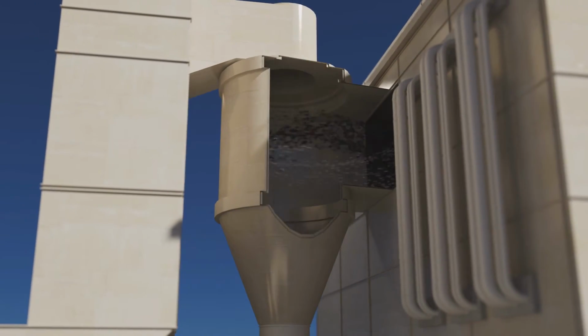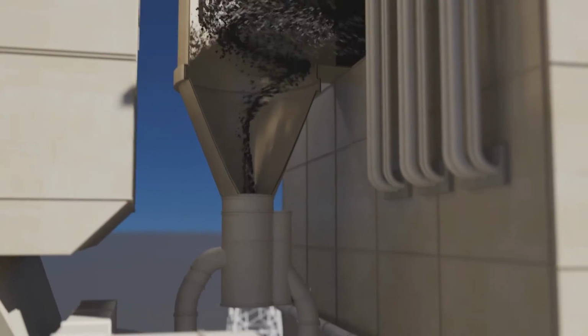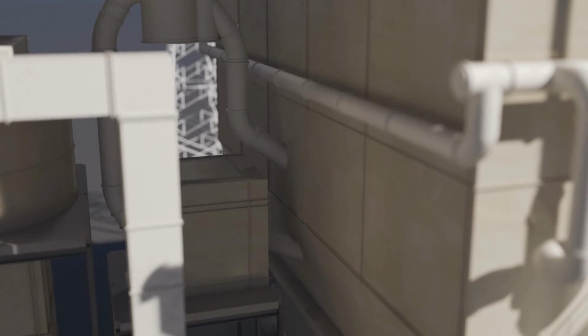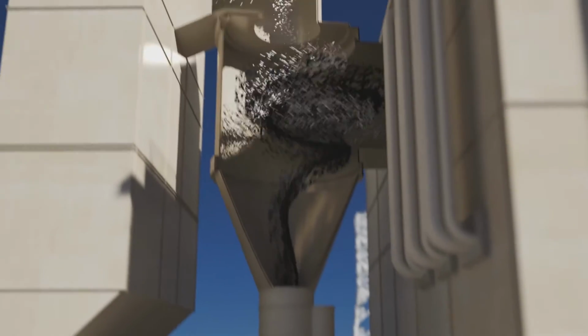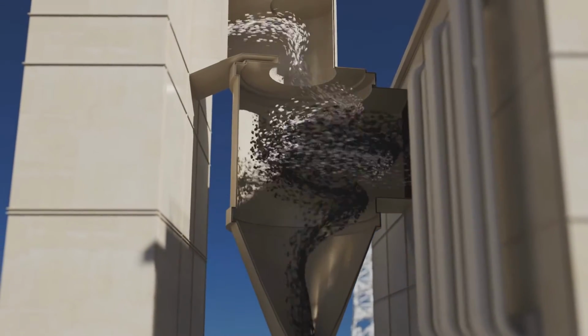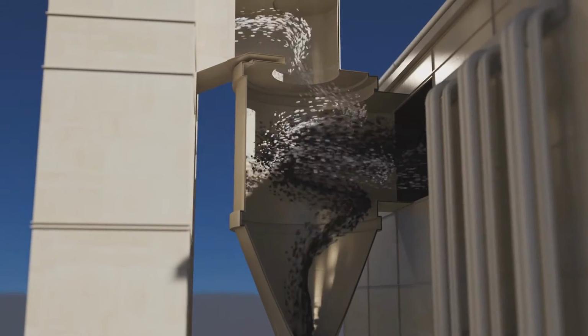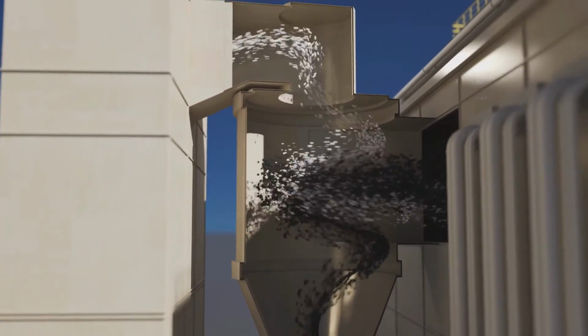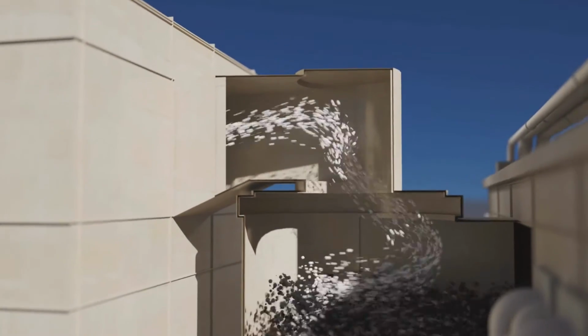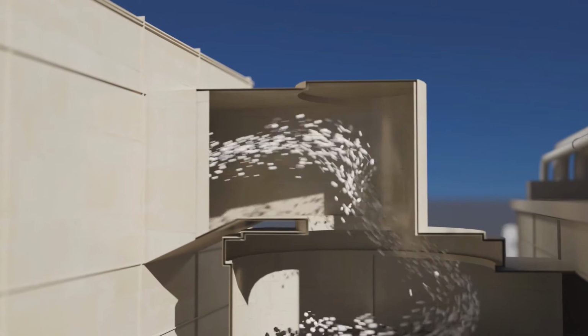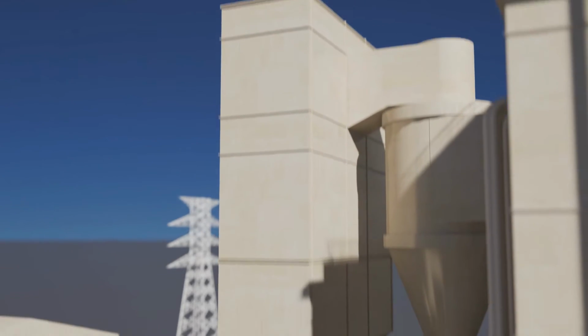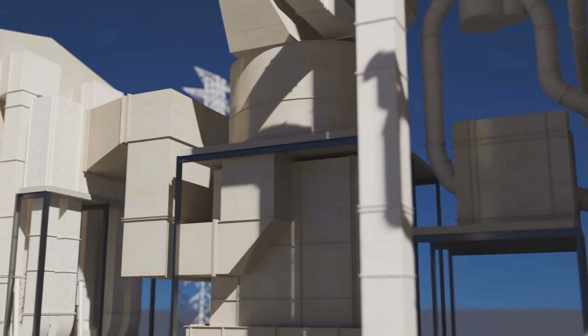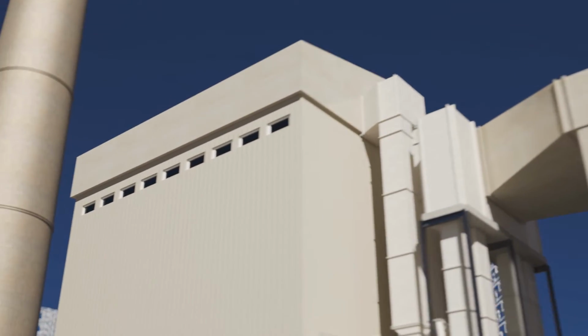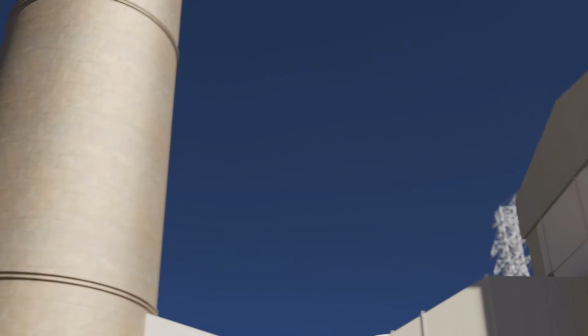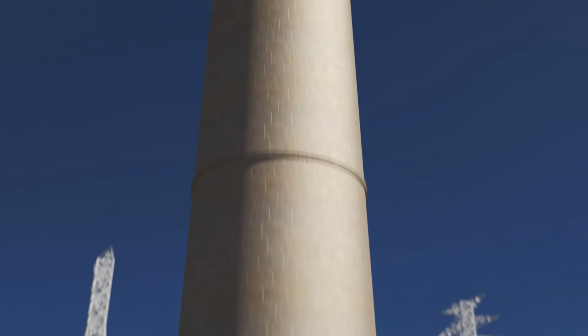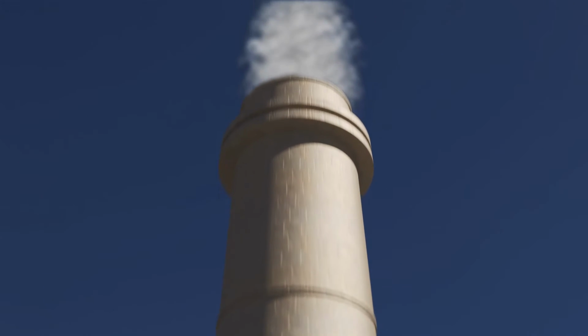The coal particles are still too heavy to exit the cyclone, so they are fed back into the boiler's combustion chamber. They make this circuit, cyclone to combustion chamber, about 2 or 3 times before all combustible material is consumed, and they are light enough to exit the cyclone. The particles, now ash, are in the flue gas, and it's this ash that gets trapped in the bag house, which works like a huge vacuum cleaner with bags to remove particulates. The flue gas, now stripped of ash particles, exits the stack, colorless, odorless, and completely in compliance with EPA standards.